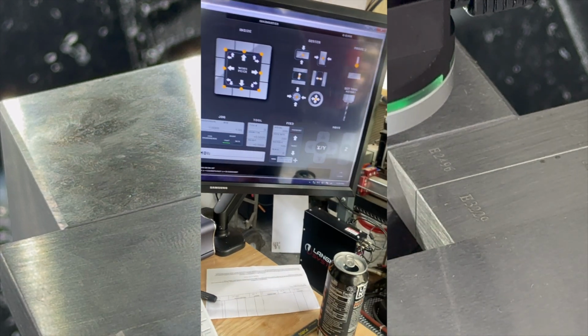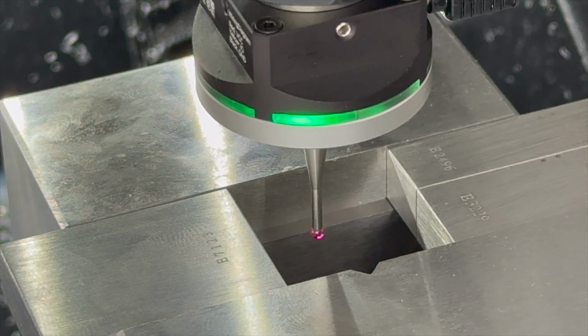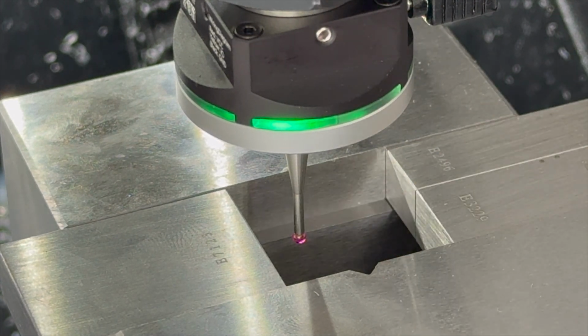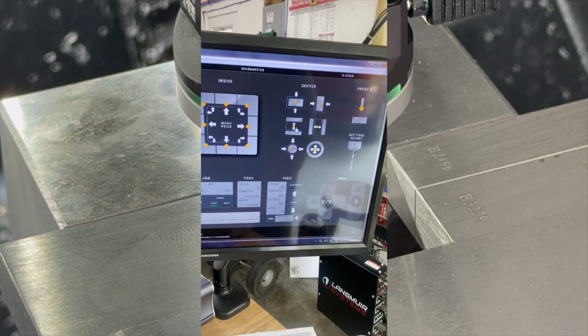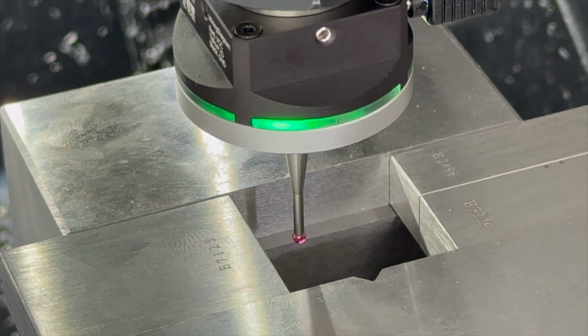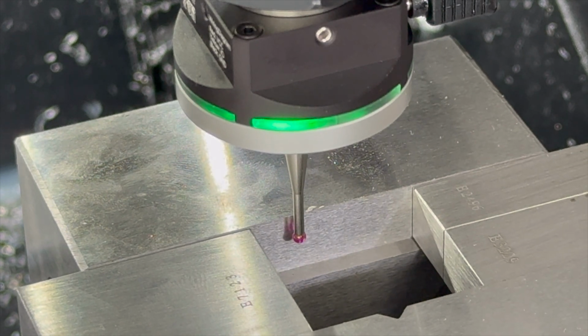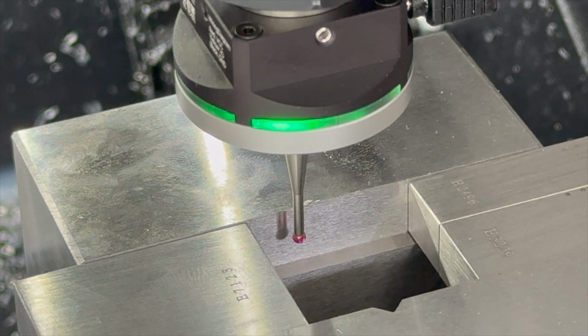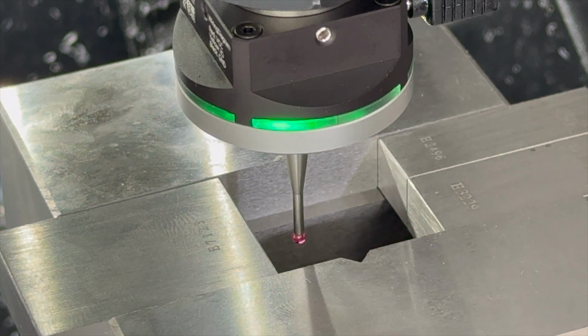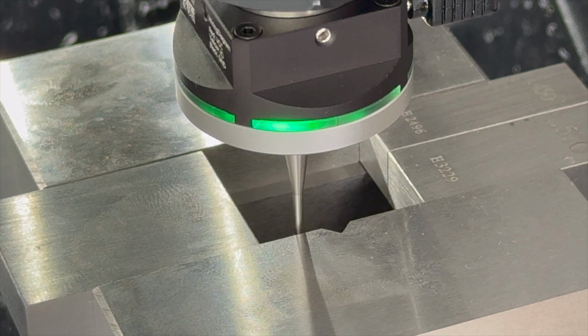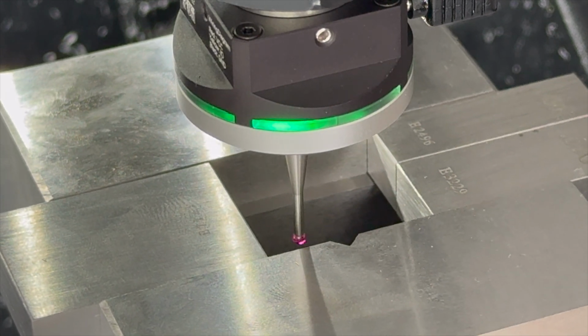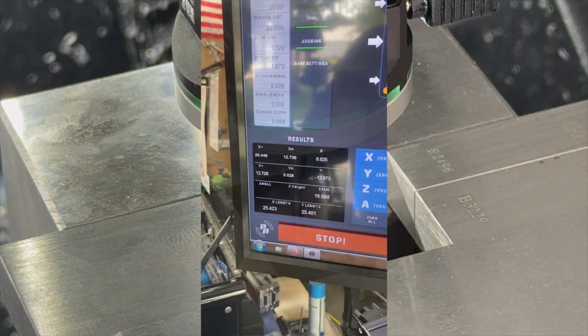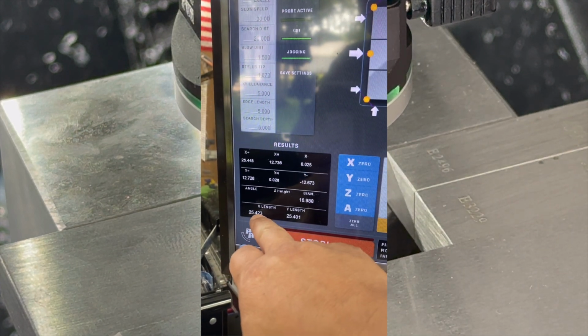All right, now we're gonna do the same thing in Y. But I want to move the probe a little bit to the left to avoid that notch right there. All right, same thing, front to back this time. Click that, and again, what we want to see is this number to be as close as possible to 25.4. Let's go back to the other side. And let's just see what we have here. All right, in this case, 25.401, that's right on the money. Normally what you see is these two numbers to be pretty close to each other. Just for the hell of it, let's just do another front to back and see what that does.